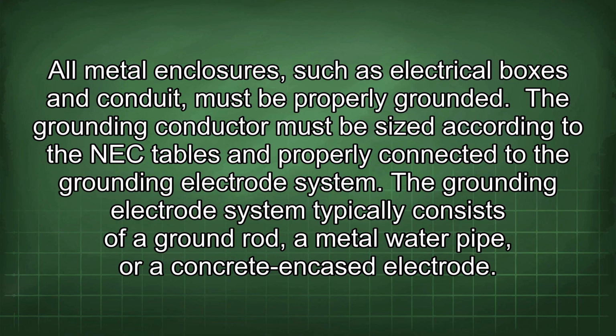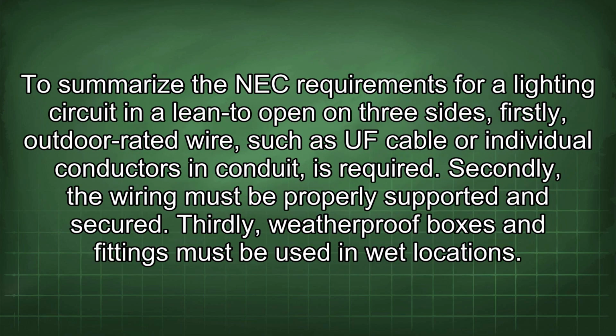The grounding conductor must be sized according to the NEC tables and properly connected to the grounding electrode system. The grounding electrode system typically consists of a ground rod, a metal water pipe, or a concrete encased electrode. To summarize the NEC requirements for a lighting circuit in a lean-to open on 3 sides: firstly, outdoor rated wire, such as UF cable or individual conductors in conduit, is required.